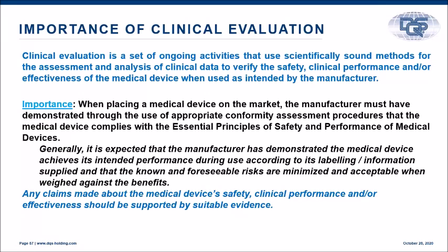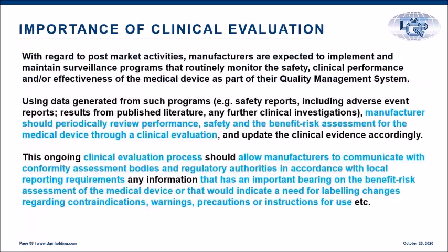So when placing a device on the market, the manufacturer must have demonstrated through the use of appropriate conformity assessment procedures that the medical device complies with the essential principles of safety and performance of devices. So this is the requirement which is there in the regulation as well. So any claims made about the medical device's safety, clinical performance, and/or effectiveness should be supported by suitable evidence. So that evidence is through your clinical evaluation reports.